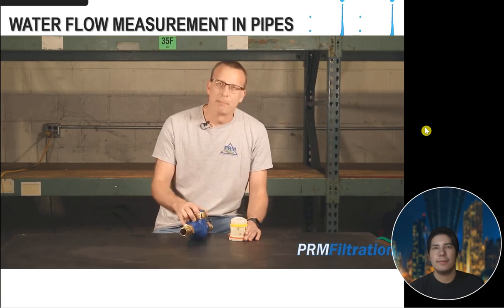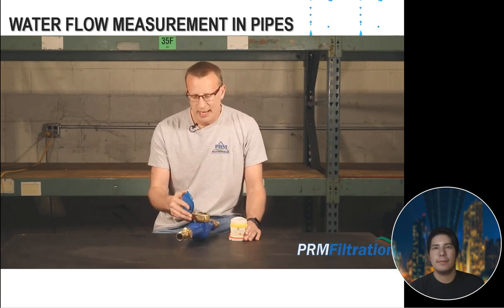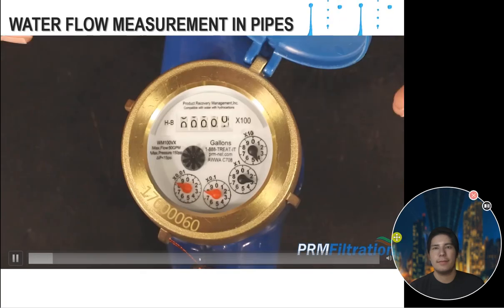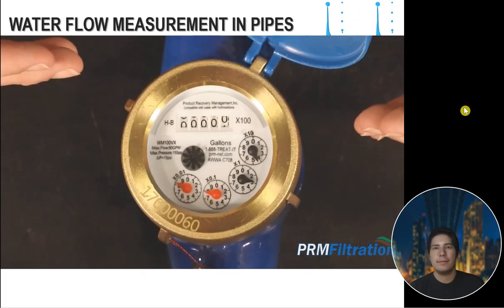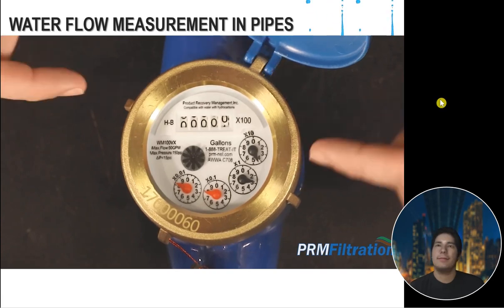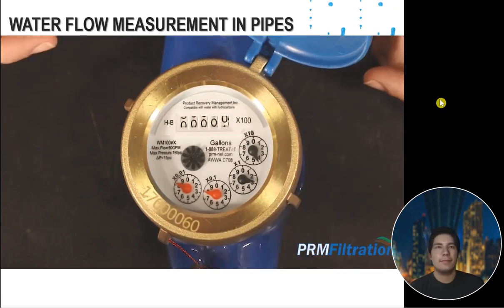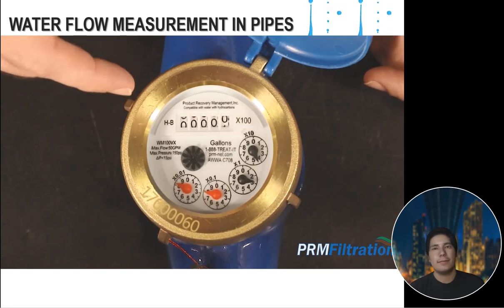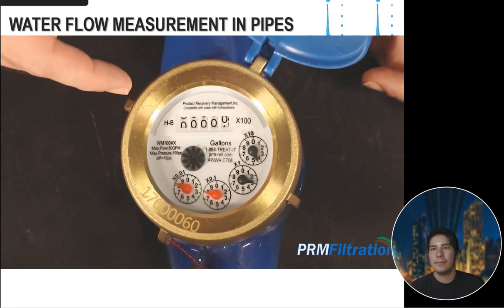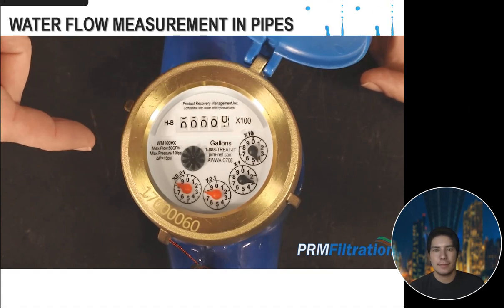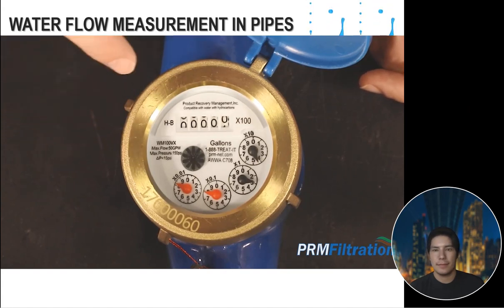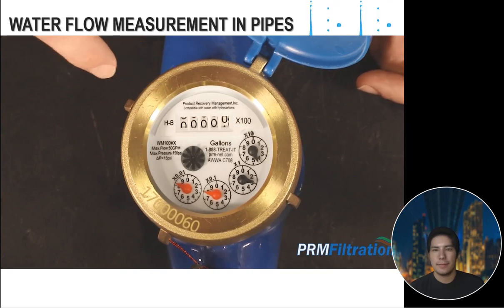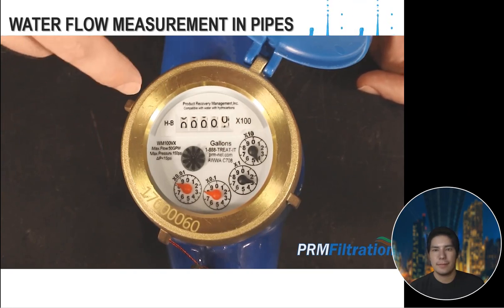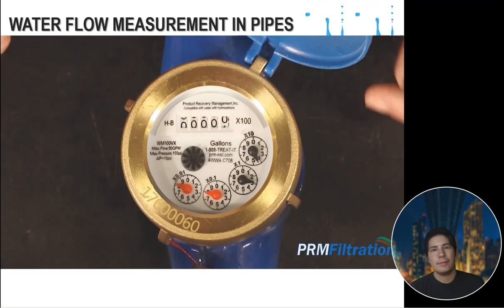PRM filtration. Today we're going to be talking about the multi-jet PRM water meters and about how they work and how to read them. So when you are reading your meter, you have to look at the dials as well as the counter. The counter is every 100 gallons. This 1-inch meter has a max flow of 50 gallons per minute, so your counter is not going to be spinning all the time. Just because your counter is not spinning does not mean the meter is not working.